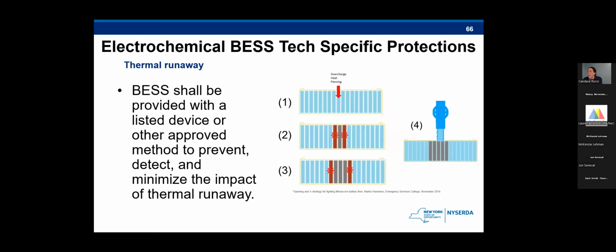And then next we have the thermal runaway, which is something that we had talked about earlier. And once it starts, it cannot be stopped. So energy storage systems should have a device that can recognize when that temperature is rising, and the device should isolate that area and send a signal to the owner of the system that a problem exists. That device is the battery management system. So also data has shown that stopping the charging and discharging of a cell is an effective measure to prevent a cell from going into thermal runaway. So on the right of the screen, it shows the stages of what a thermal runaway event can look like. A method must be in place to prevent the cell from going into thermal runaway and prevent the spread to adjacent cells.